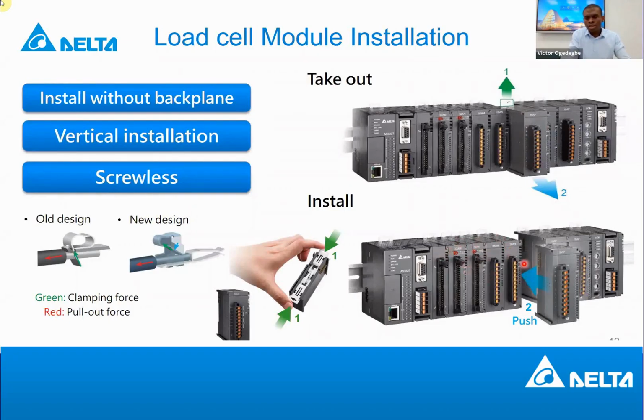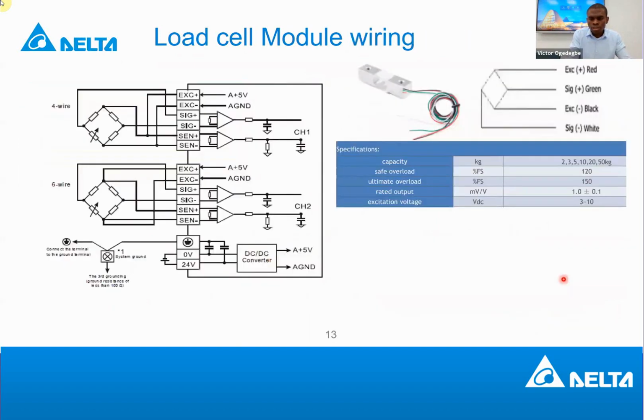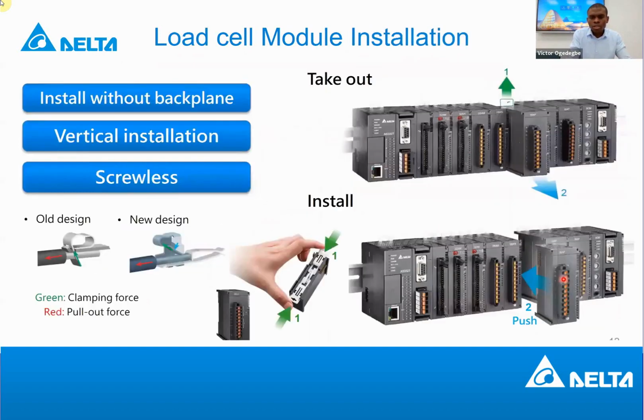Once you install it to the right-hand side of the PLC, the PLC knows that the load cell module is at this position. When it comes to the time of address mapping, the CPU will map the corresponding address to the load cell module that you have added to it. I will show you the configuration that I have here during the wiring session.